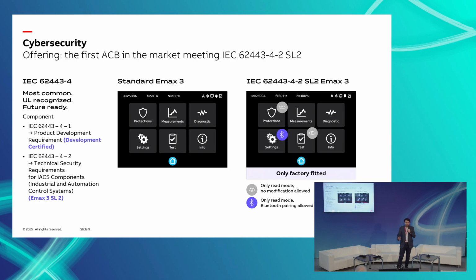The difference is that on the cybersecurity circuit breaker, it's not possible to change parameters on the HMI. Why? Because we are not able to recognize who is touching or modifying parameters. So this is the first level of protection for people who can change parameters.